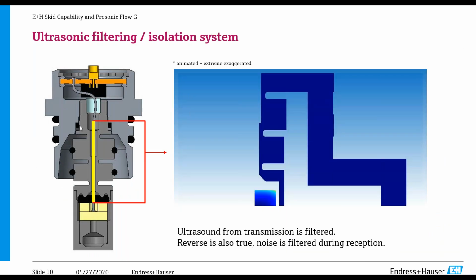As you know, when we transmit, the other transducer is looking to receive. And what we don't want is that these piezos are generating sound, and the noise from the piezo goes out one direction into the gas, but it's also going back into the transducer and into the meter body. And this can run around the pipe inside the metal and be transmitted to the other piezos, creating noise in the system. And so what we want to do is filter this out.